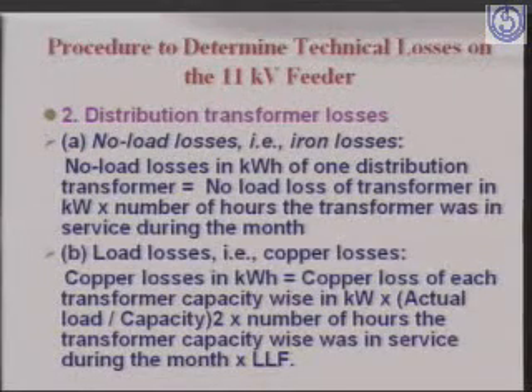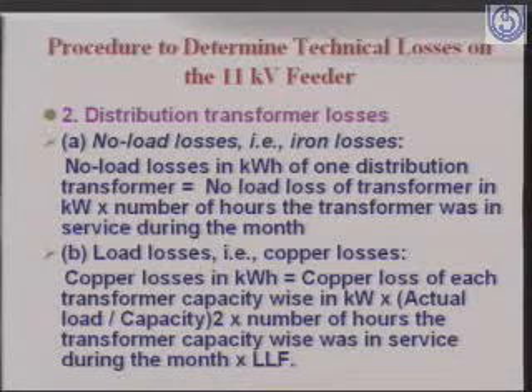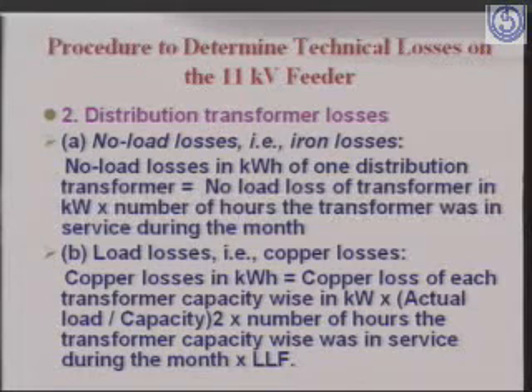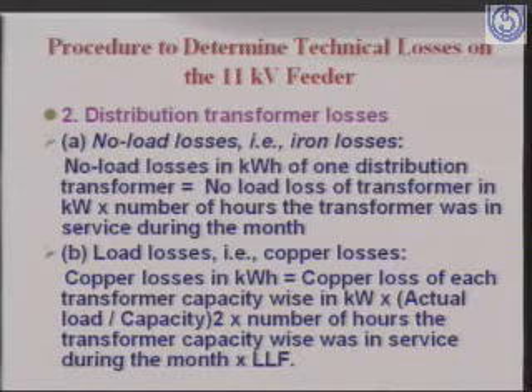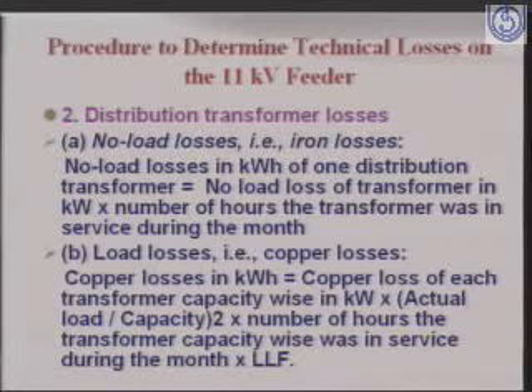Now, distribution transformer losses. Basically we know there is the no load loss and the load loss. The no load loss is mentioned on the nameplate rating of the transformer. It is very easy to work out. It is fixed as long as the voltage is fixed. In case you have transformers which are operating at lower or higher voltage, then you need to apply certain correction factors. But for all practical purposes, you can take whatever the nameplate rating is, multiplied by the number of hours the transformer is in service.